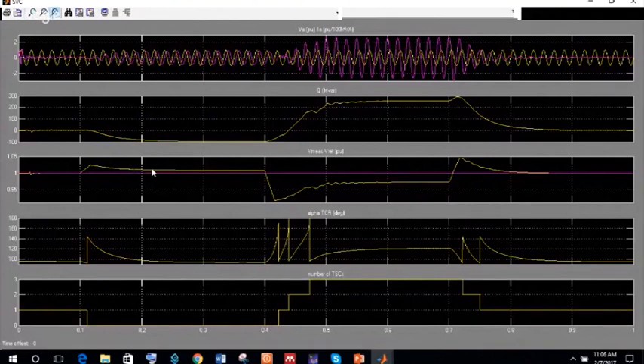So the increased value of voltage should be brought back to its reference. This can be done by absorbing the power. Power absorbed means it is shown here as negative. Power is absorbed by the inductor, that is the TCR, thyristor controlled reactor, which makes this firing angle 140 degrees, and the thyristor controlled reactor is taken into service. When the voltage has dropped, it should again be brought back to its reference.